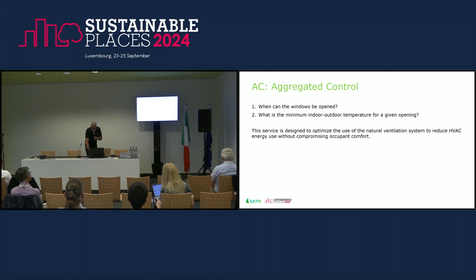The main challenge in a building with openable windows is not deciding when to close the windows - that's easy, because it's getting hot. Say it's summer, so clearly you need to close the windows and turn on the HVAC. That's an easy decision for any control system. The main struggle is deciding when we can open the windows and keep them open, because we could open them in a given building and then say, oh, it's not good, let's close them and turn on the HVAC again.